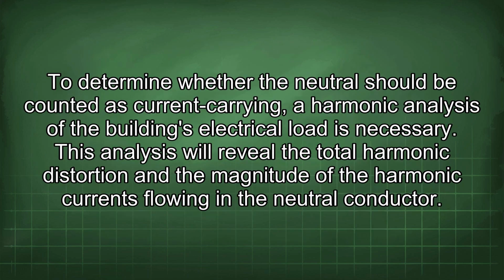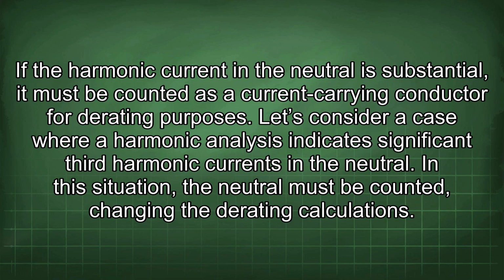To determine whether the neutral should be counted as current carrying, a harmonic analysis of the building's electrical load is necessary. This analysis will reveal the total harmonic distortion and the magnitude of the harmonic currents flowing in the neutral conductor. If the harmonic current in the neutral is substantial, it must be counted as a current carrying conductor for derating purposes. Let's consider a case where a harmonic analysis indicates significant third harmonic currents in the neutral. In this situation, the neutral must be counted, changing the derating calculations.